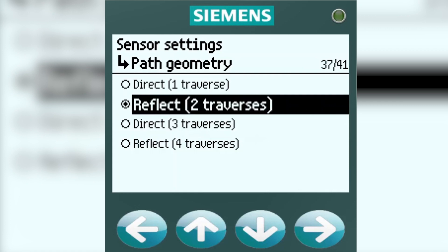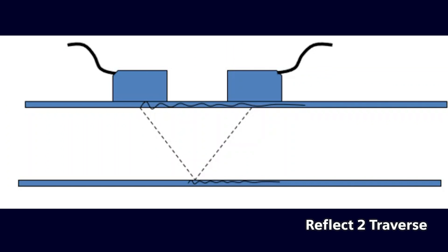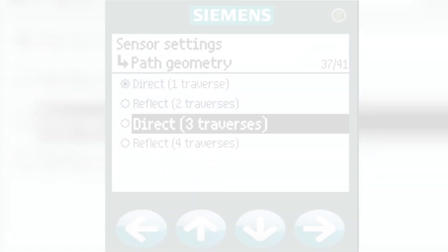Reflect 2-Traverses. This is the same top view, except both sensors are on the same side of the pipe, and there are 2 passes, or traverses, inside the pipe. This is typically used for steel pipes, whenever there's enough space, and whenever the pipe diameter is large enough to accommodate this.